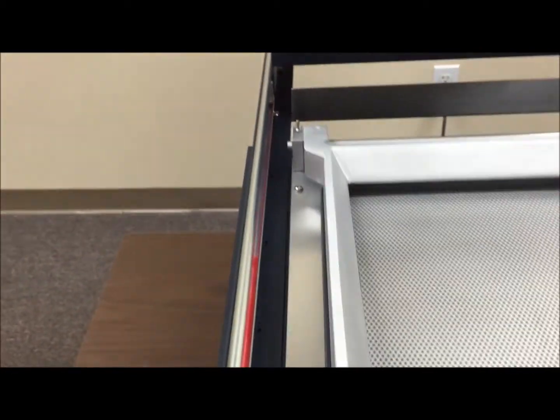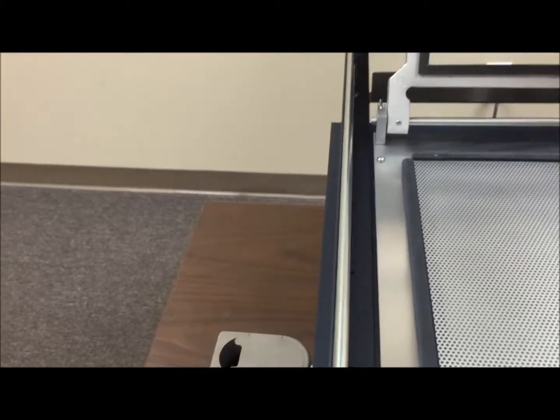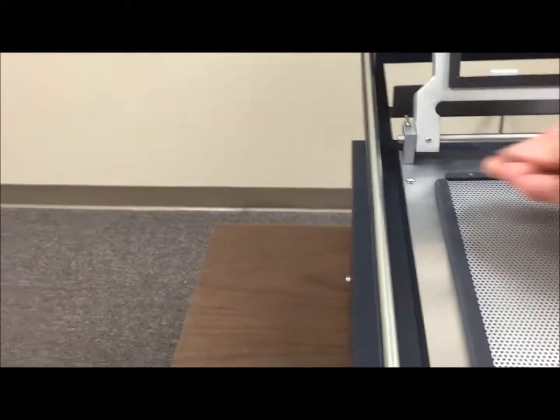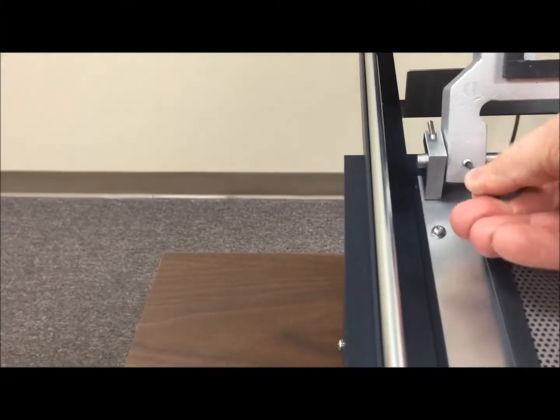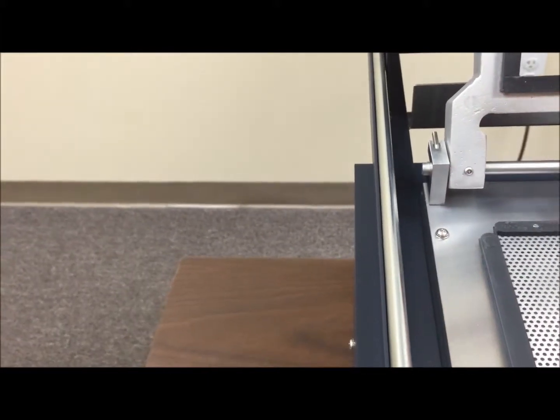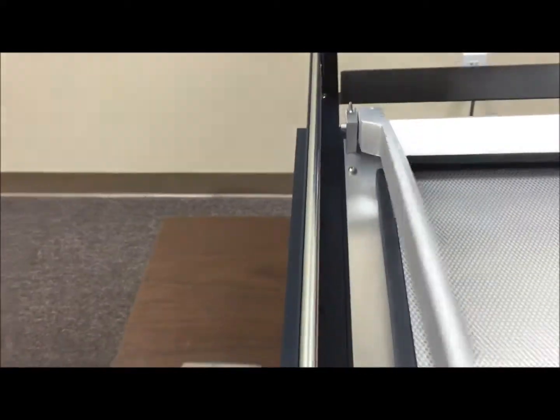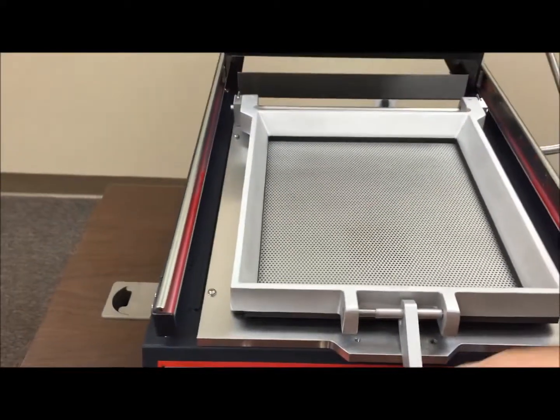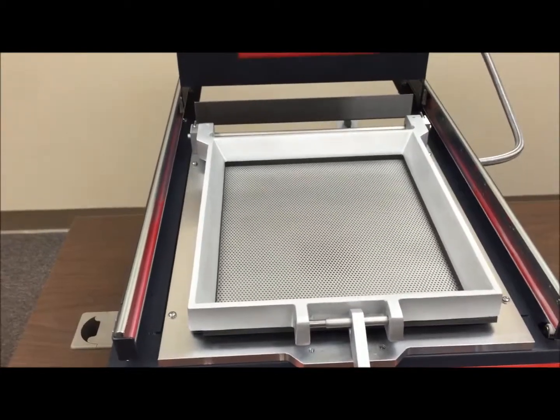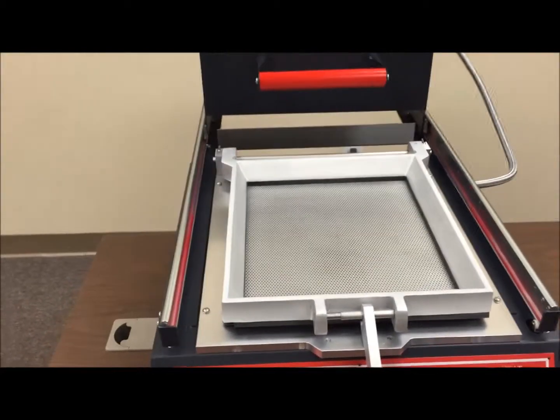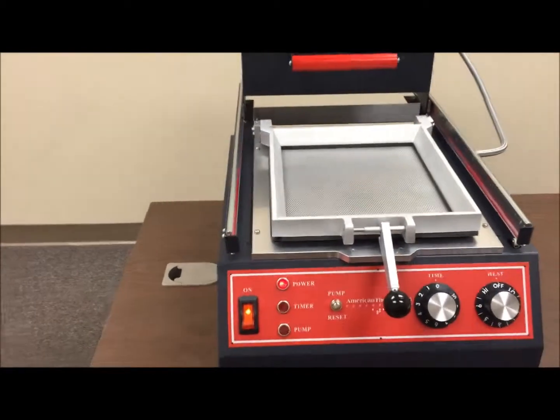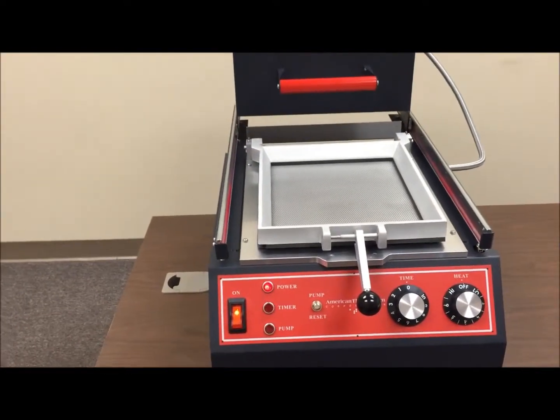So you'll loosen these, and then you will, on this side, you will tighten this set screw. So it raises the bar up, therefore making it a tighter seal when it comes down. So those are two common areas that you'll have to maintain after using your Thermoform machine.